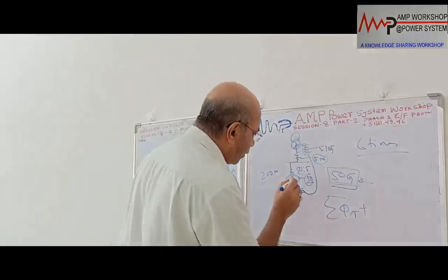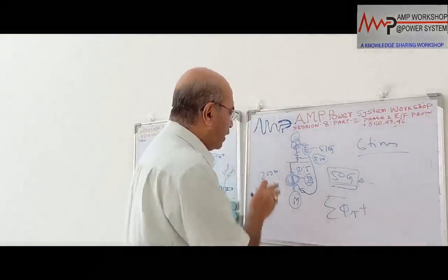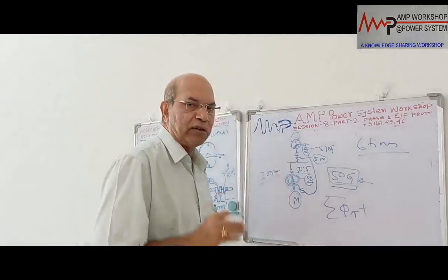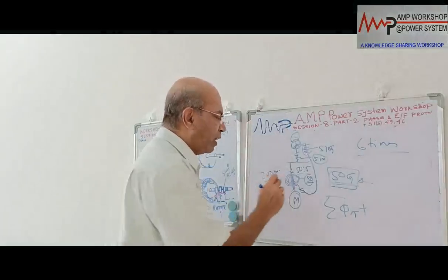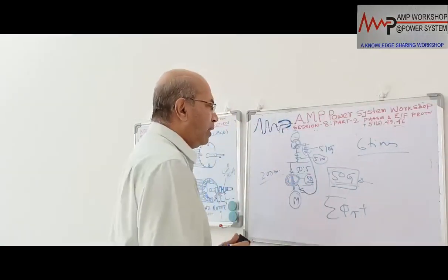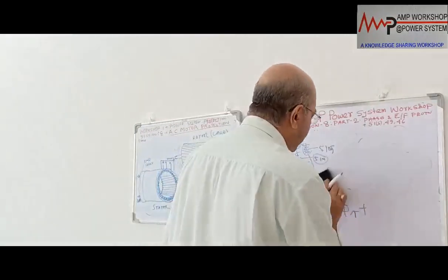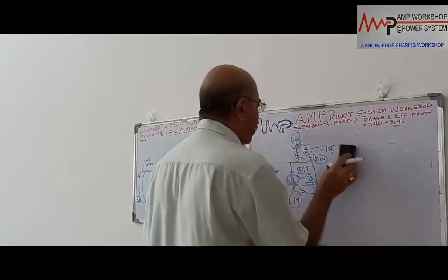But if the cable is of such a diameter that it cannot go through the donut CT or CBCT, and a CBCT is not available, then we cannot provide 50G in that way. In that case, we will provide the instantaneous earth fault protection in a different way.